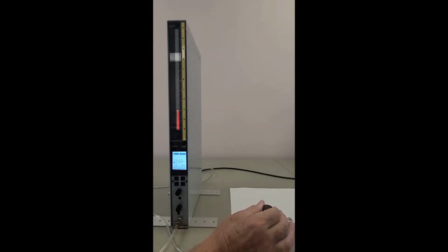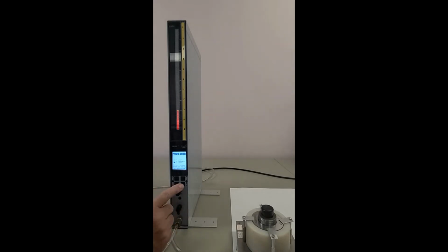So if I turn a part in the fixture and there is variation as it turns, you'll see the display being able to move back and forth. And it will hold the maximum value it sees until reset. Now I've programmed the two lower buttons of our display, the U1 and U2. U1 turns TIR on or off, and U2 I've programmed to do a TIR reset. So I'm going to put the air on first, and we'll just see how this works.